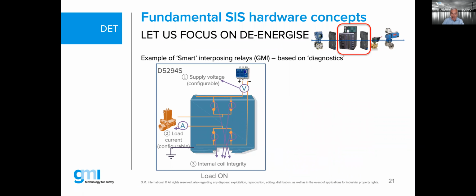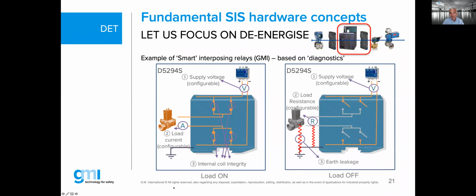And I give you here two examples, left and right. On the left-hand side, here we're going to put the load on. That means if this is a normally open contact, all those contacts need to be closed, in order to drive the load, in order to keep the solenoid energized. In order to de-energize, the simple answer is we have to open the load, we have to remove the power, and that is the purpose of using such a relay as we show here on the left-hand side.